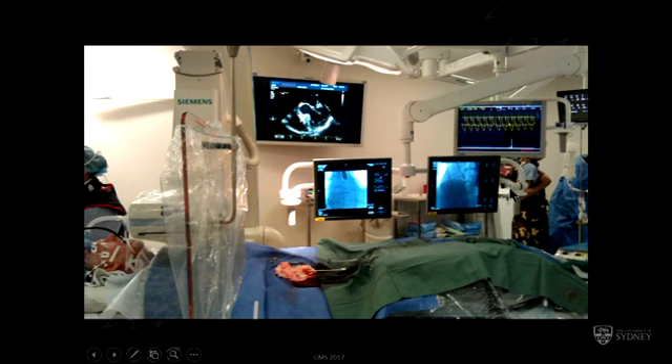This is typically the world of the hybrid operating room, with a full operating suite and full cath lab all in one room, lots of televisions. The key feature from my point of view in these rooms is that everybody can see everything — the cath guy has to be able to see the echo, and the echo person has to be able to see the angiogram, so that you're all on the same page. There is a complete set of monitors for the echo person.